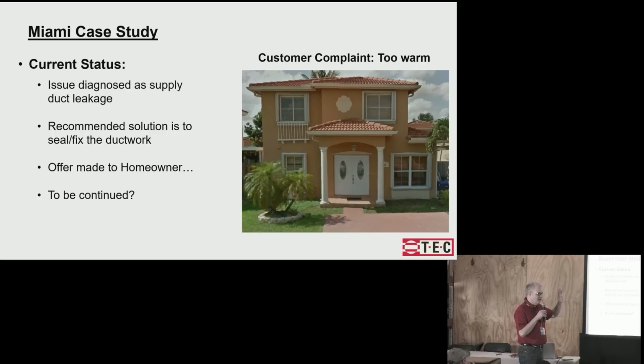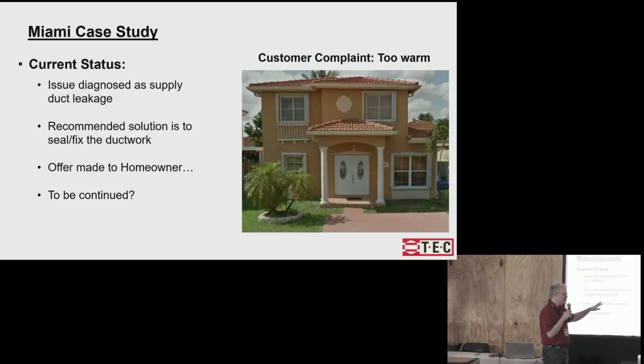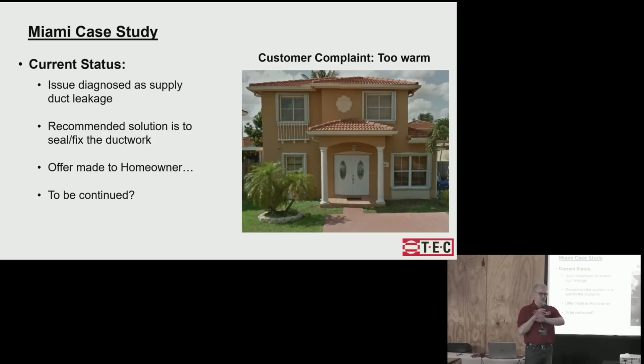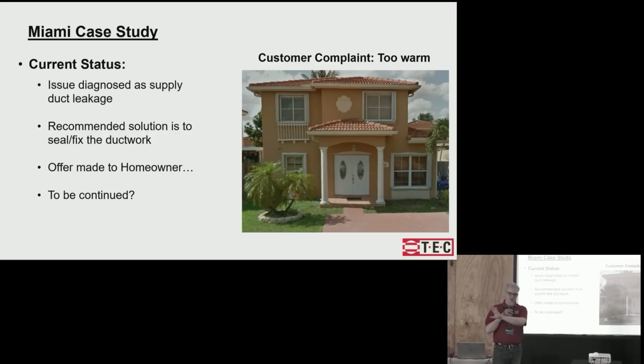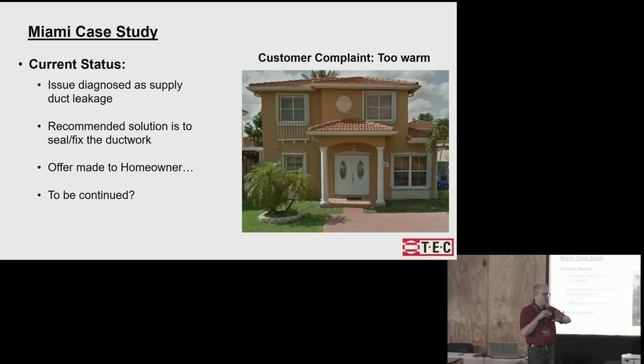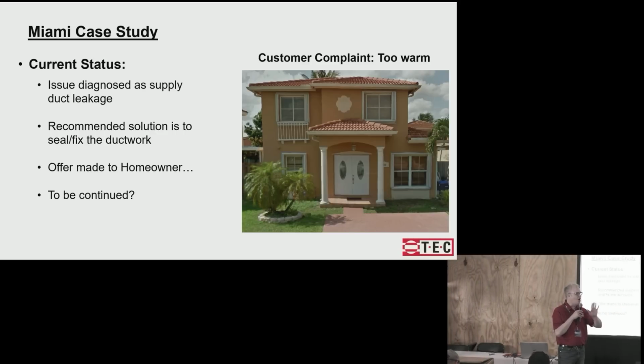Okay, that problem is almost always an infiltration problem. If you do a blower door test on that house, what you're going to find is that it's probably not too leaky, but all the leakage is into the bonus room. The way that they're built, it's horrible. So your Manual J is going to say it's good, but Manual J assumes that the infiltration load is spread equally through the whole house, when the reality is it's all in the bonus room.